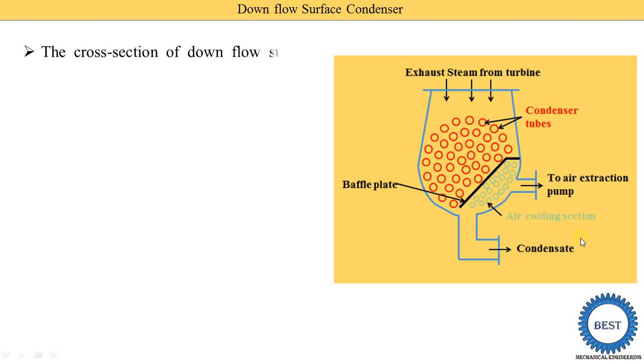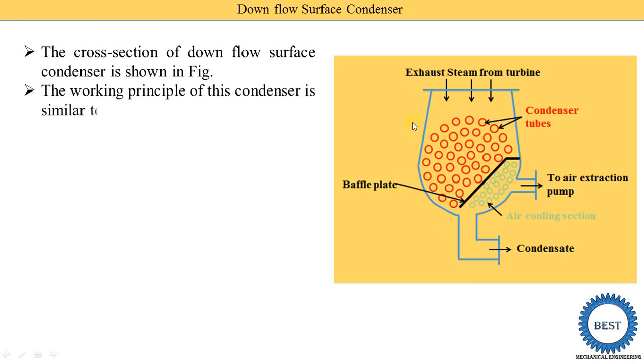In this diagram you see the cross section of the downflow surface condenser. The working principle is similar to the double pass surface condenser — water passes two times for the full length of the condenser. It is a surface condenser, meaning between the steam and the water there are some mediums, and these mediums are the tubes.